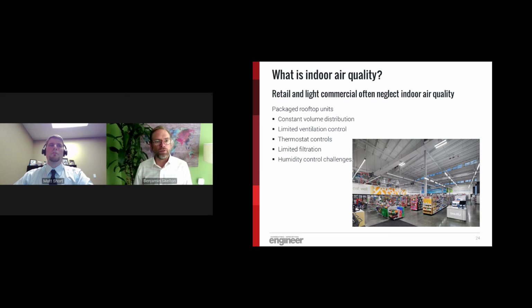And then another example is retail and light commercial sector. Often these buildings are somewhat neglected when it comes to quality HVAC systems. Generally speaking, a lot of them get packaged rooftop units, which have limited functionality when it comes to being able to do other things like demand control ventilation, for example. They tend to be constant volume distribution systems. And what we see in a lot of retail applications, restaurants, things of that nature, is they'll be on thermostatic controls that cycle. So the fan and the ventilation will only operate when there's a demand for cooling or heating. And obviously in a populated area, that's not the proper way to manage that.